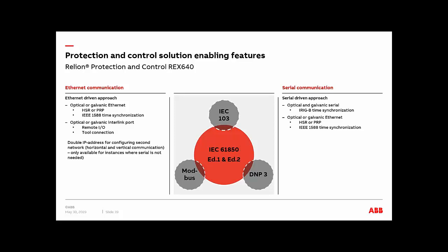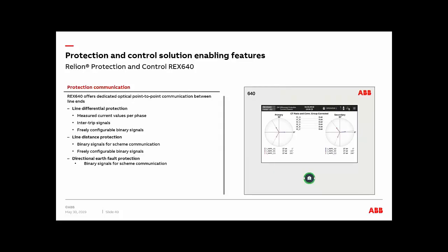You got the option of having a double IP address for configuring a second network, horizontal and vertical communication. So if you don't have serial, you could do this one as well. It's just a matter of how you arrange your different interfaces in the port itself. And if you have the serial, you can have the option for IRIG-B time synchronization. And you can have serial, optical or galvanic Ethernet for HSR or PRP. So protection communication, for protection specifically, we offer a dedicated optical point-to-point communication between line ends, specifically for the line differential protection.